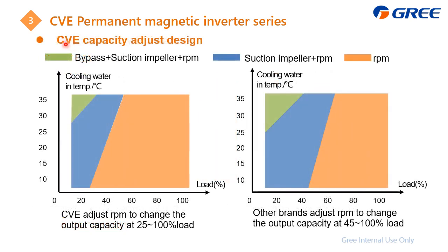This is how the CVE can adjust the capacity. On the left side is the CVE and the right side is for other brands. For the CVE, in this orange color zone, it is just by the RPM, which means we change the compressor RPM to adjust the capacity. And you can find that we can be as low as 25%, compared with other brands, which is up to 45%. The second method is to adjust the suction impeller, which is the suction vane plus the RPM, to adjust the capacity. And last is the bypass method to adjust the capacity.